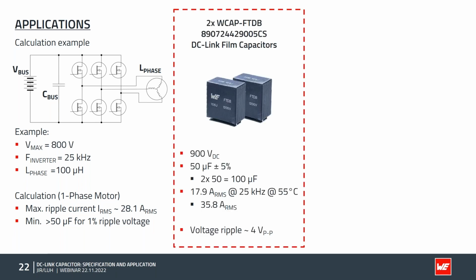So one way to do this would be using two parallel film capacitors of the FTDB series. This specific part number is rated at 900 volt DC and also 50 microfarads, so we have more than needed capacitance. Also, the maximum RMS current of this capacitor is only 17.9 amperes, so we have a total of...